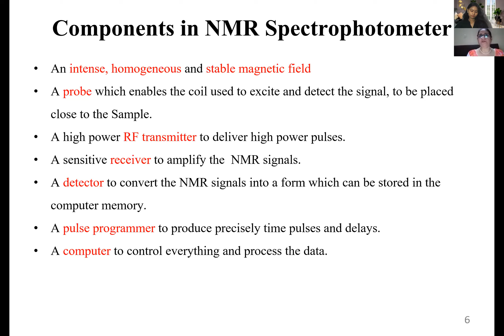There is an intense, homogeneous and stable magnetic field, a probe which enables the coil used to excite and detect the signals to be placed close to the sample, an RF transmitter to deliver high power pulses, a sensitive receiver to amplify the NMR signals, a detector to convert the NMR signals into a form which can be stored in the computer memory, a pulse programmer to produce precisely timed pulses and delays, and a computer to control everything and process the data. So now let us look into each part of the spectrophotometer.